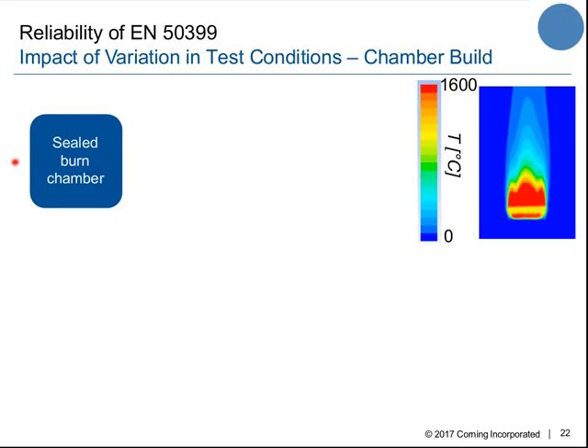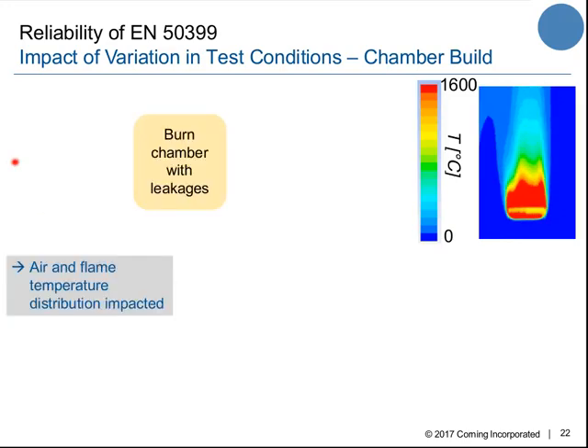If we are now adding some leakages to our chamber, do you see that the temperature distribution is now shifted again to one side, like you saw it before for the air distribution? So the temperature distribution in the flame is now asymmetric, shifted to one side. That means that the temperature distribution in the flame is also very sensitive towards changes of the sealing of our burn chamber. So we were interested, can we prove that in practice?